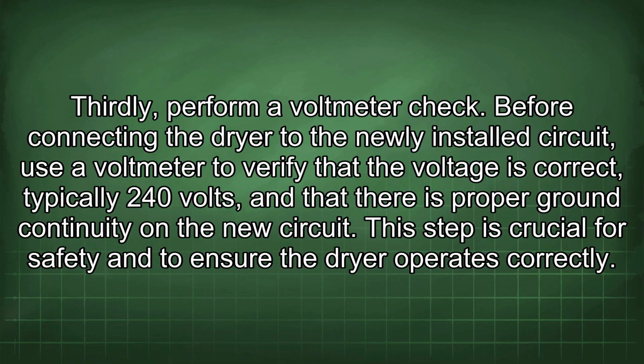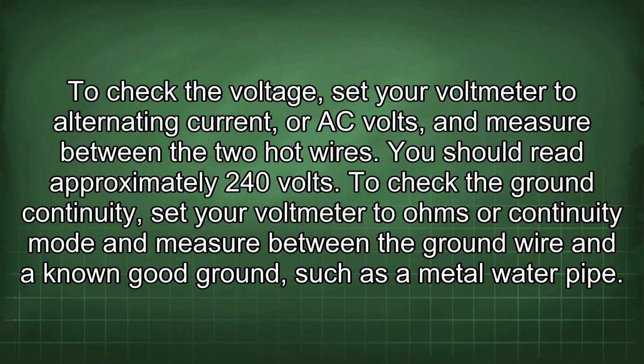Thirdly, perform a voltmeter check. Before connecting the dryer to the newly installed circuit, use a voltmeter to verify that the voltage is correct, typically 240 volts, and that there is proper ground continuity in the new circuit. This step is crucial for safety and to ensure the dryer operates correctly. To check the voltage, set your voltmeter to alternating current, or AC volts, and measure between the 2 hot wires. You should read approximately 240 volts.